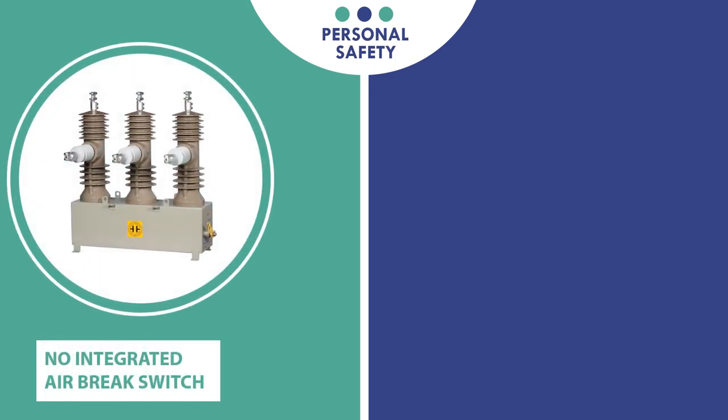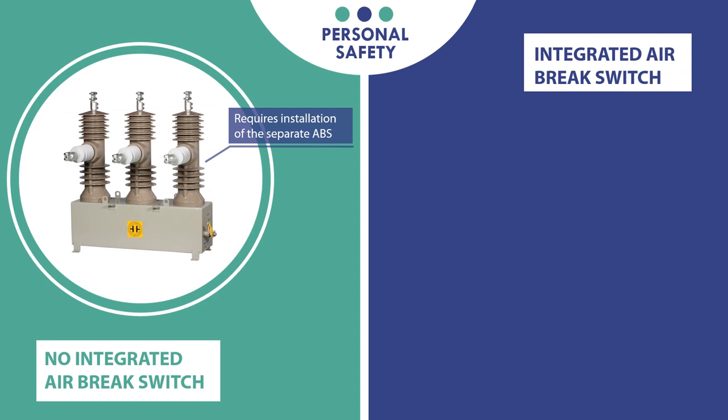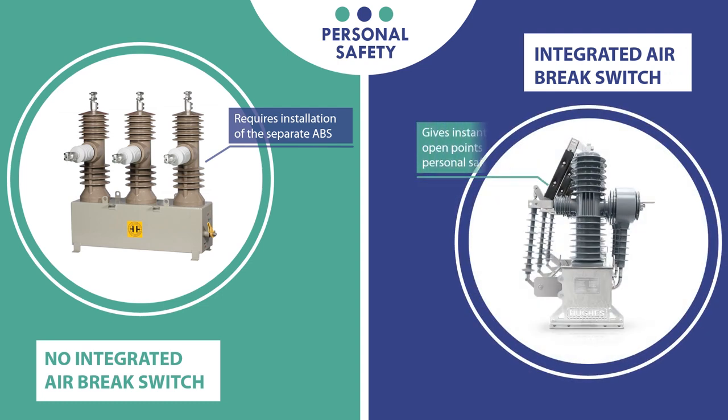Moving forward to the next important factor: personal safety. All other manufacturers do not provide built-in air break switch, which means that it needs to be installed separately on another pole. Hughes provides optional integrated air break switch, which gives 3 visible open points for enhanced personal safety of linemen. This option has lower cost compared to a separate device.